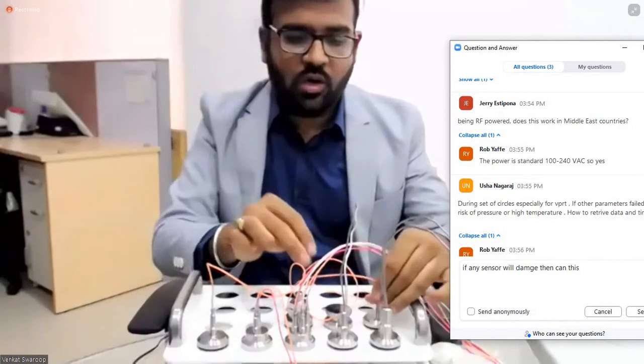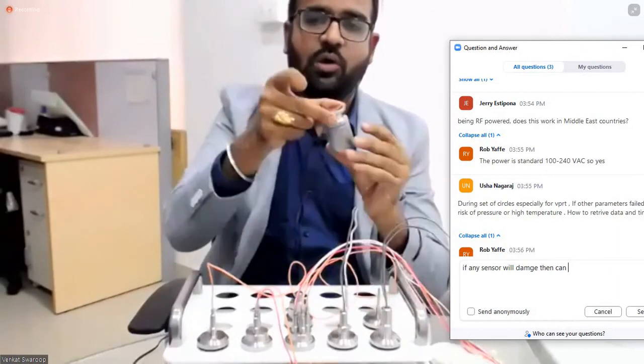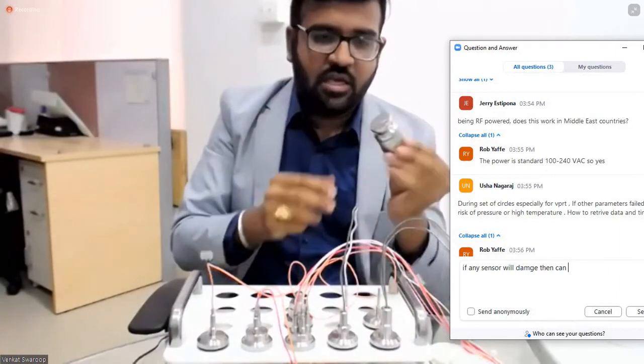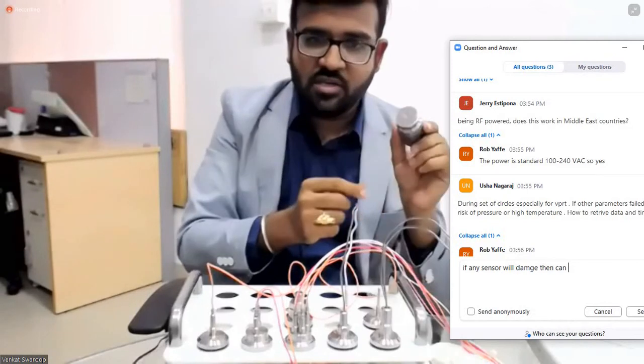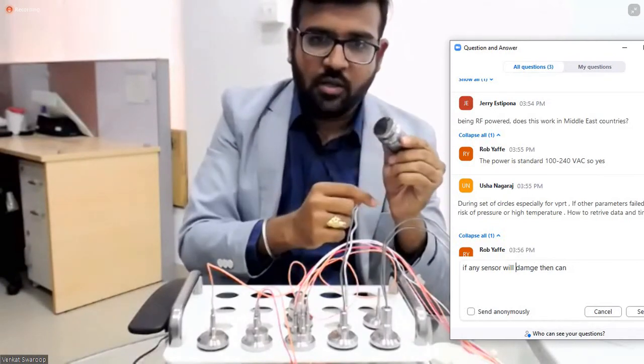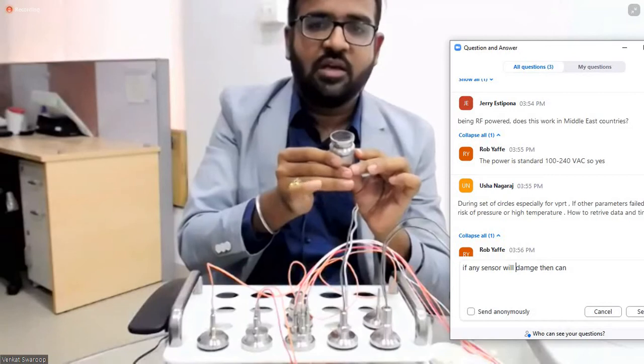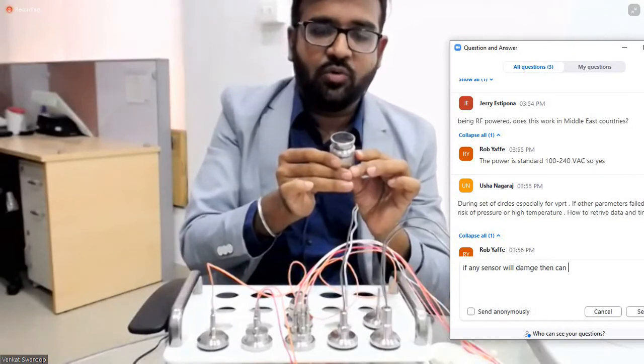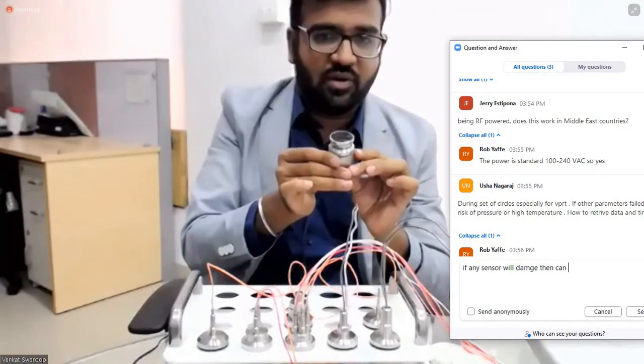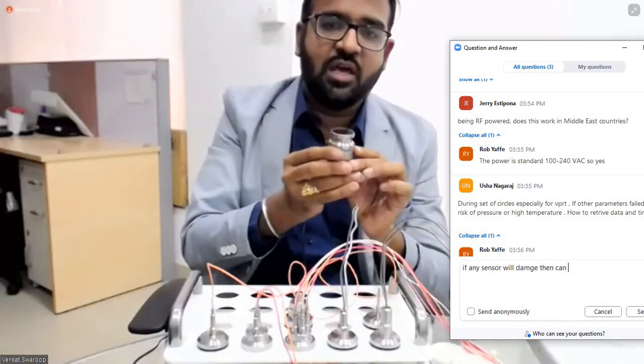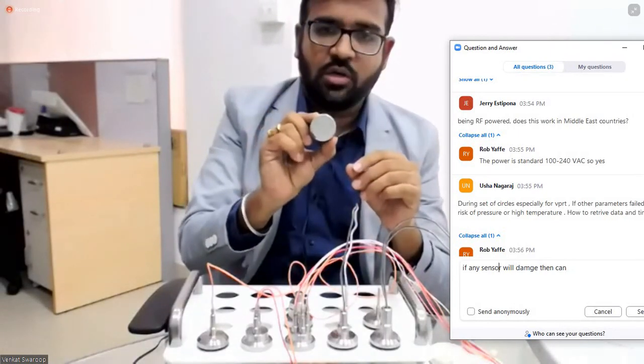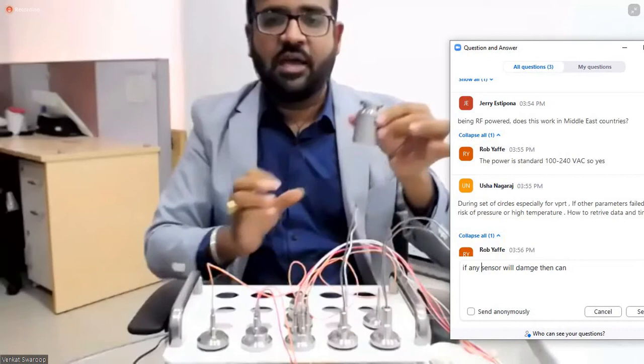One more logger is the flat surface logger. The logger looks like this. The beauty here is the sensor is placed on top of the logger, and while performing shelf validation in your lyophilizers for surface measurement, you have to use this logger for lyophilizer activities.